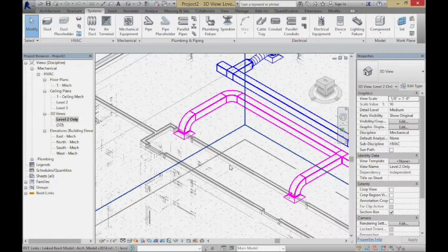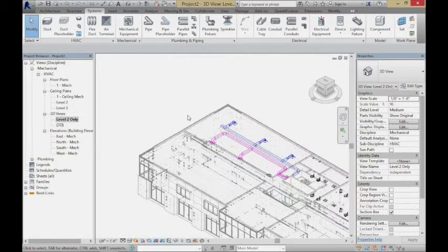Which is more expensive, the hard duct or the flex duct? The flex duct is definitely less expensive. It's just the hard duct's a better efficiency, better performing system, but more precision in the field. Flex duct, cheaper, easy to install, but over the next 30 years, someone's going to pay for it. Yeah, so that's the essential trade-off. Okay, so you've got two examples here.